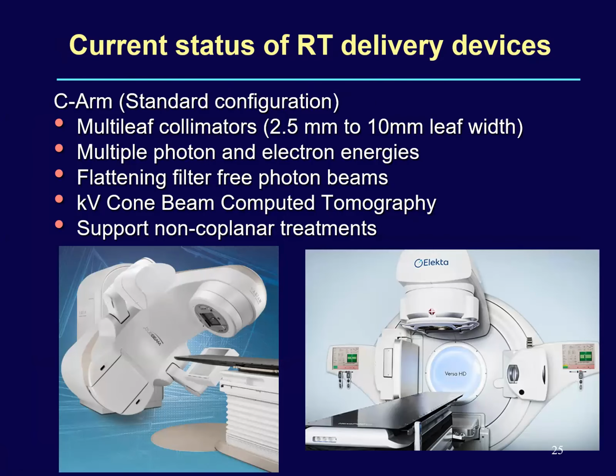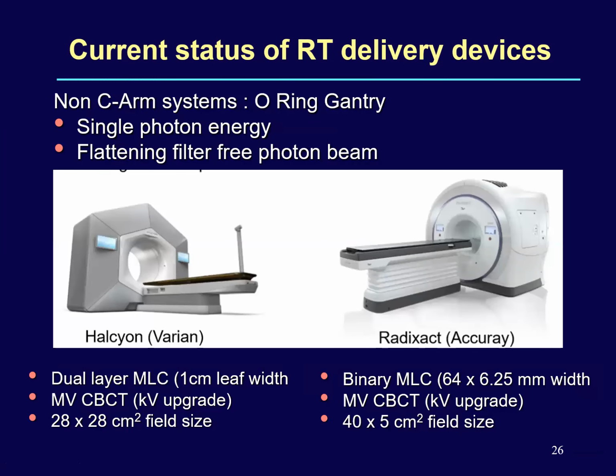So look at the current status of the delivery systems. It can be grouped as C-arm, because we have C-arm type linear accelerators, which we conventionally use, either a Varian TrueBeam or a Versa HD, equipped with multi-leaf collimator, multiple photon energies, flattening filter-free, KV cone beam CT, planar imaging as well. Also, this machine can support non-coplanar treatments. The other contemporary status is non-C-arm systems like the O-ring gantry, the Halcyon produced by Varian, or the Accuray Radixact, which is the advanced equipment of the tomotherapy. The Halcyon has a single photon energy with flattening filter-free photons. They have a dual layer of MLC in the Halcyon machine with MVCBCT capability, and in future they may be coming up with KVCBCT as well.